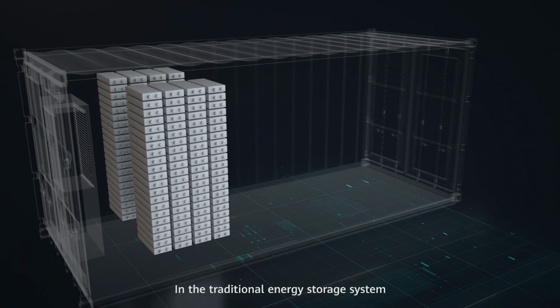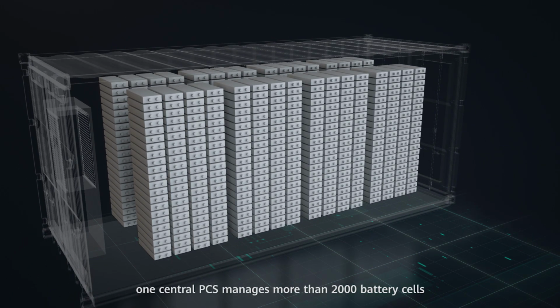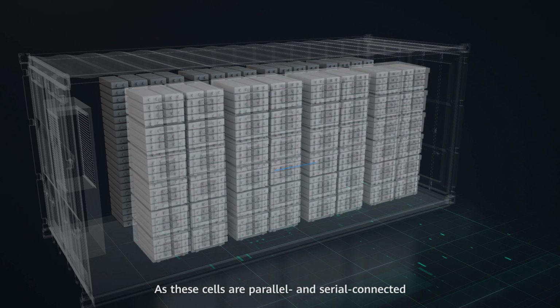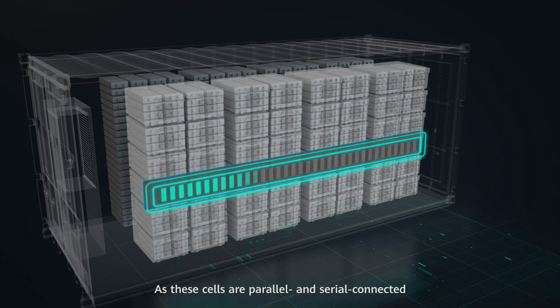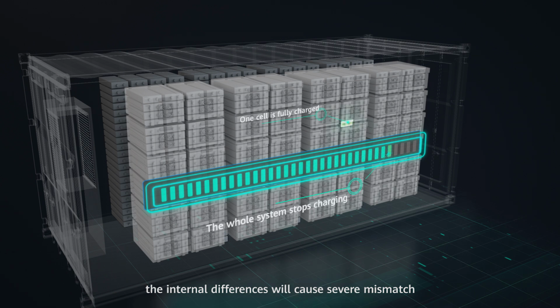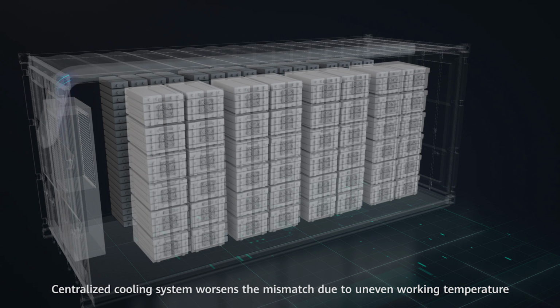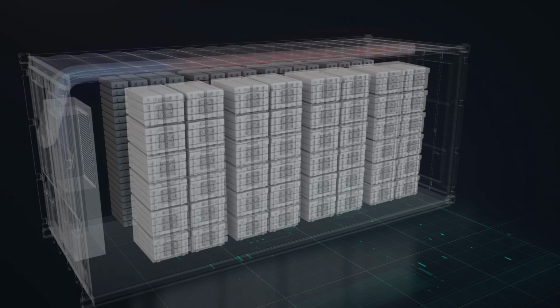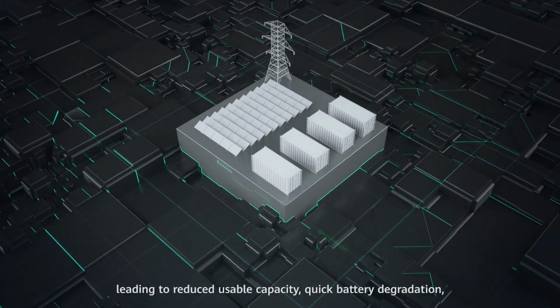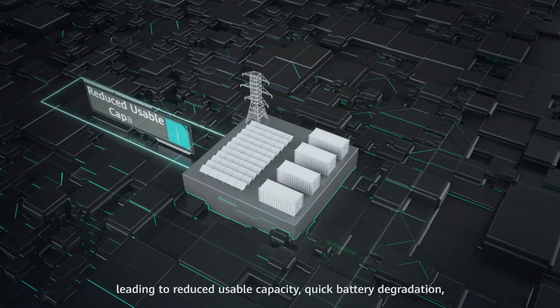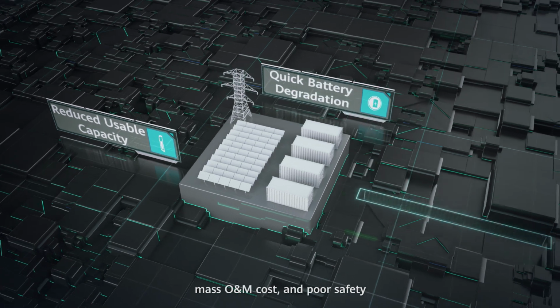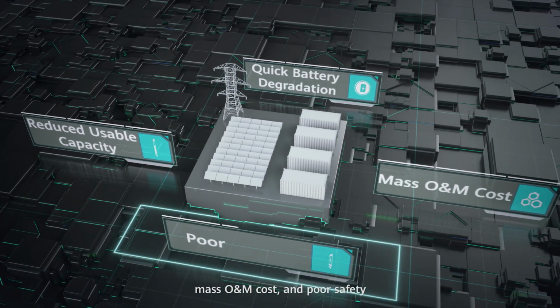In the traditional energy storage system, one central PCS manages more than 2,000 battery cells. As these cells are parallel and serial connected, the internal differences will cause severe mismatch. Centralized cooling system worsens the mismatch due to uneven working temperature, leading to reduced usable capacity, quick battery degradation, mass O&M cost, and poor safety.